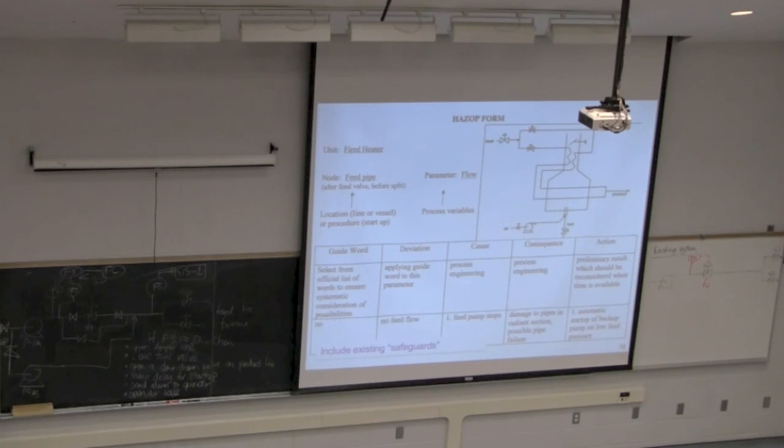Pump 1B, this loop over here is only for emergencies. It's not typical operation. So we still get that flow. Definitely want to introduce it here so we get F3 running so we don't use SIS. Then we've got a day or two to fix up that pump, fix up that wiring, while pump 1B helps us out.